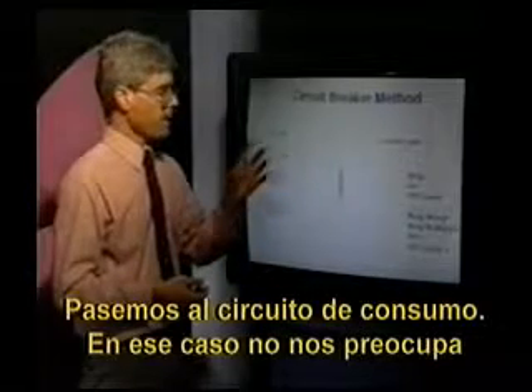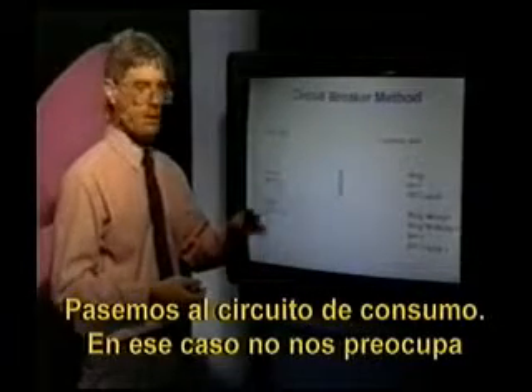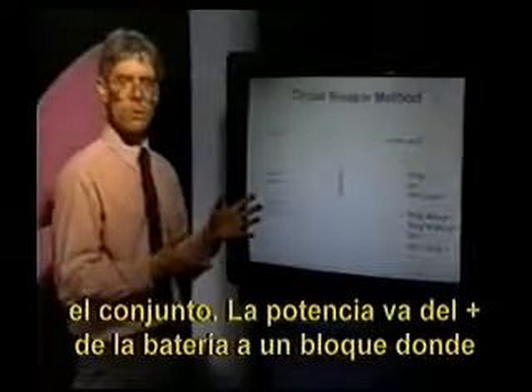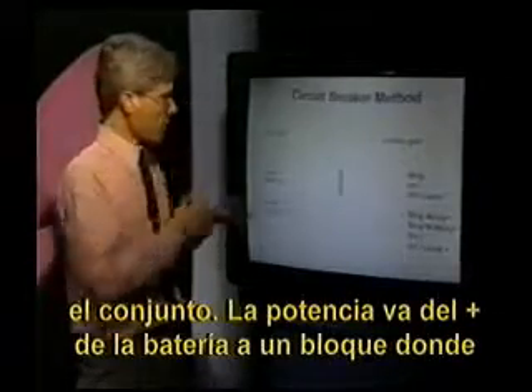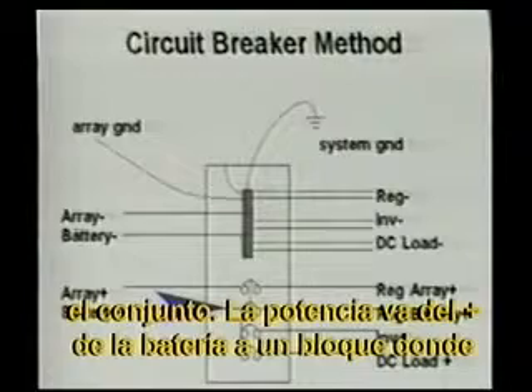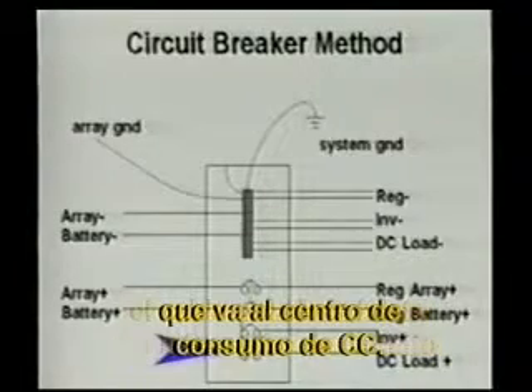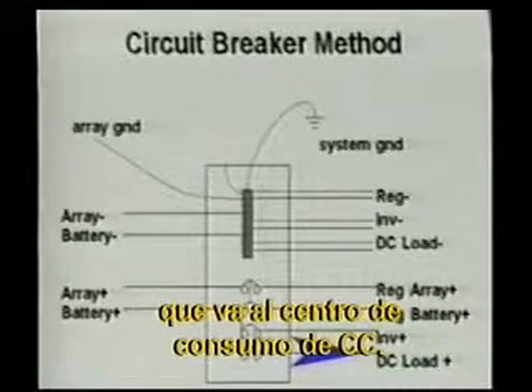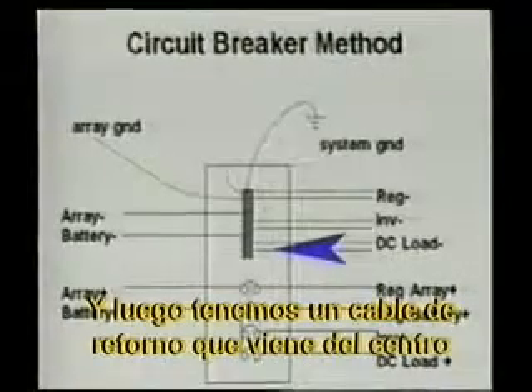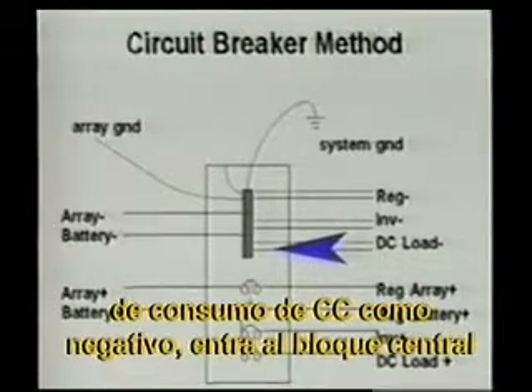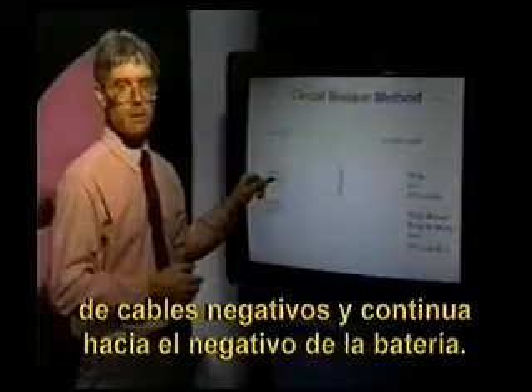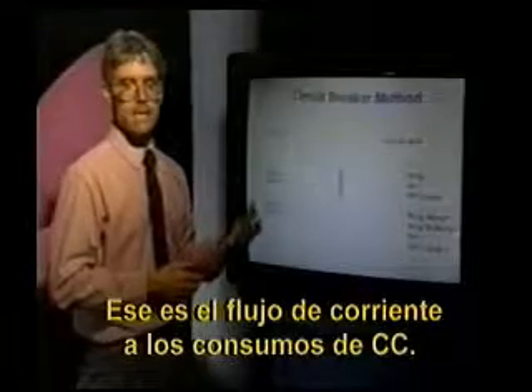Let's look now at the load circuit. In that case, we're not concerned about the array. We have power flowing from the battery plus into a block where we carry the wire across to a circuit breaker that goes to our DC load center. And then we have a return wire coming from the DC load center as a negative, coming into our central negative wiring block, going on to battery negative. There's the current flow to our DC load.